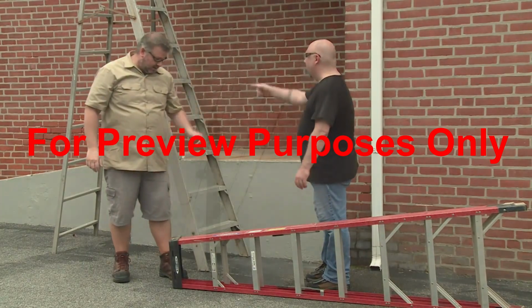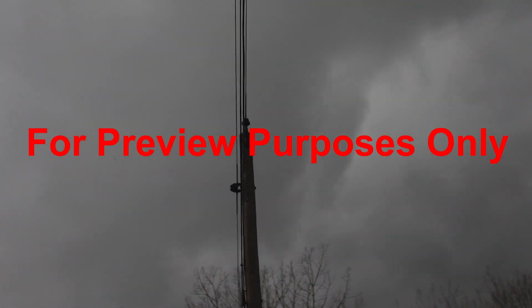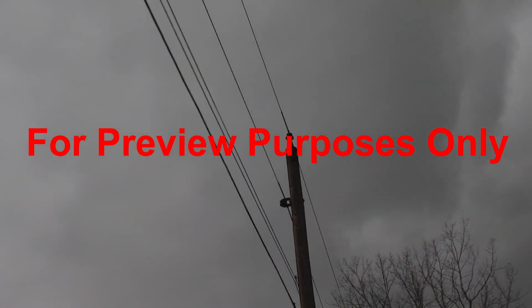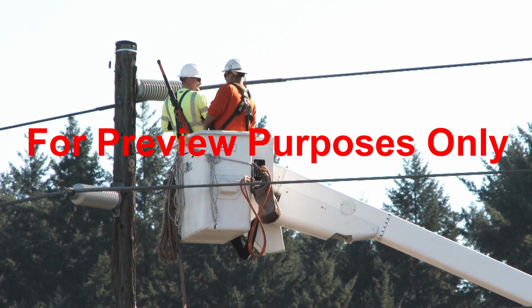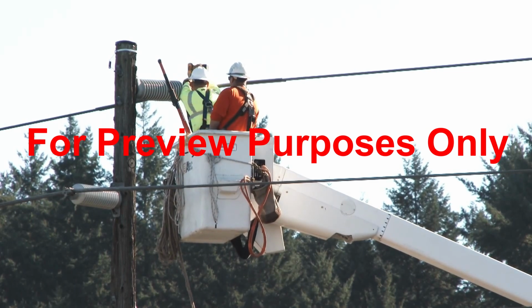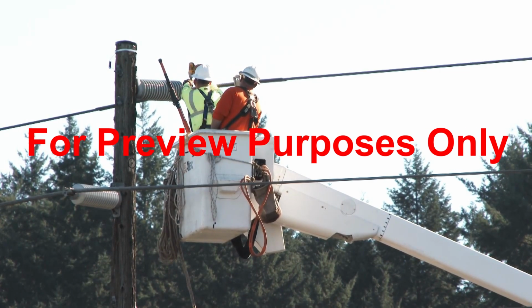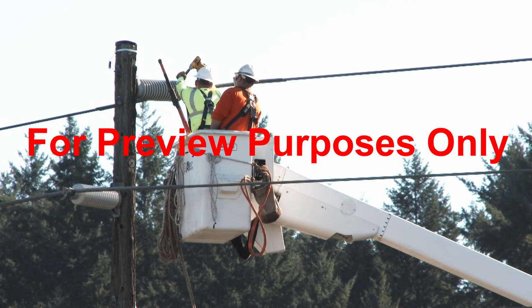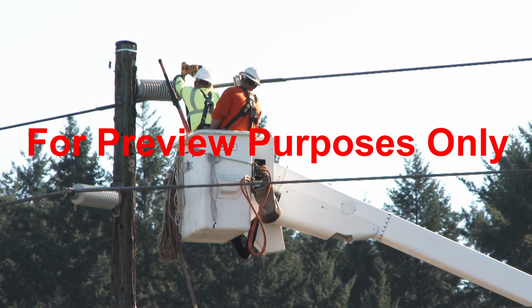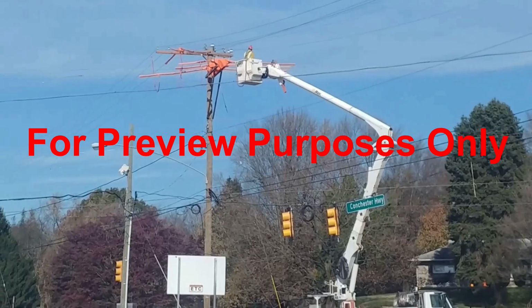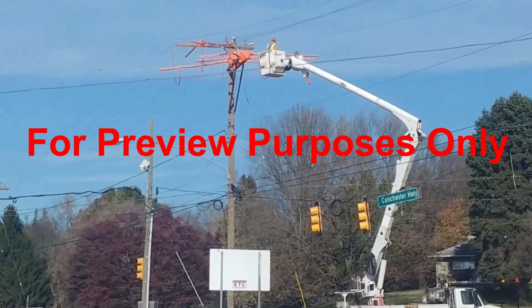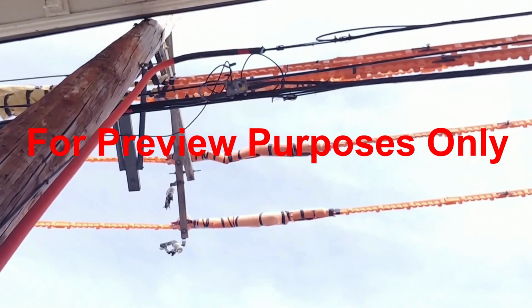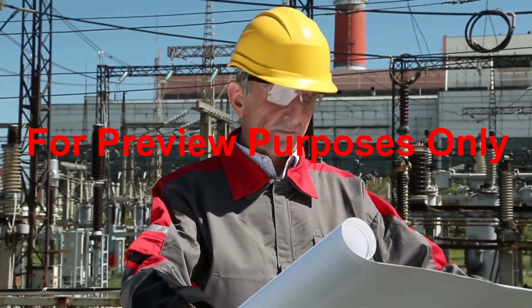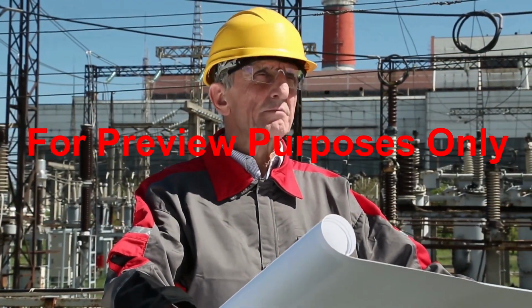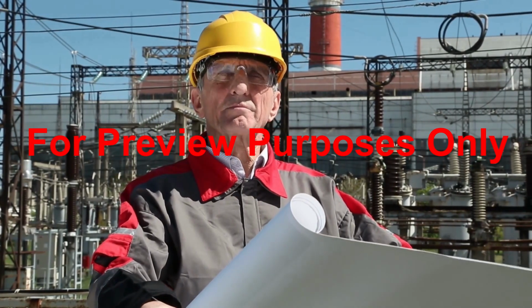While power lines do have protective coatings, they are there to protect the wires from the weather. They won't protect you from the electricity in the lines. So whenever possible, arrangements should be made with the utility company that operates the lines that are on a job site to de-energize and ground them. If they cannot power down the lines, they may be able to install insulated sleeves over them to provide some degree of protection. But for live power lines, it's also critical to determine how much voltage is being carried in the lines.